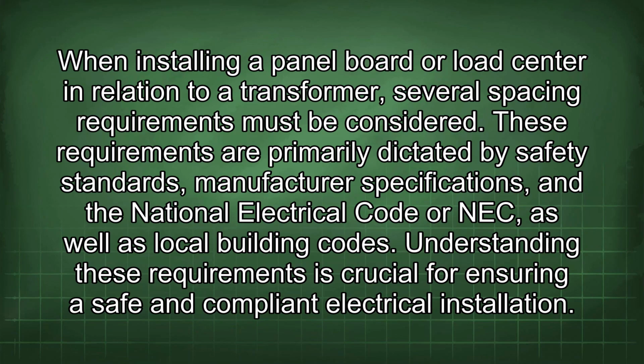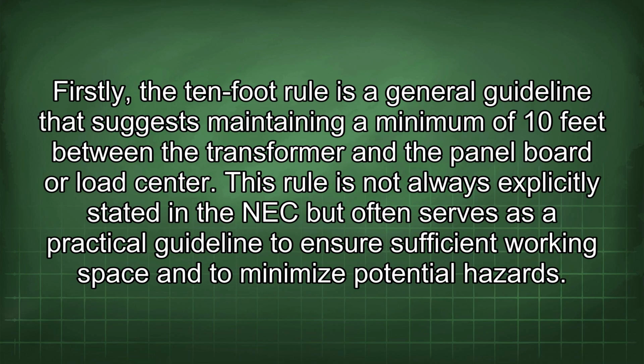When installing a panel board or load center in relation to a transformer, several spacing requirements must be considered. These requirements are primarily dictated by safety standards, manufacturer specifications, and the National Electrical Code, or NEC, as well as local building codes. Understanding these requirements is crucial for ensuring a safe and compliant electrical installation. Firstly, the 10-foot rule is a general guideline that suggests maintaining a minimum of 10 feet between the transformer and the panel board or load center. This rule is not always explicitly stated in the NEC but often serves as a practical guideline to ensure sufficient working space and to minimize potential hazards.